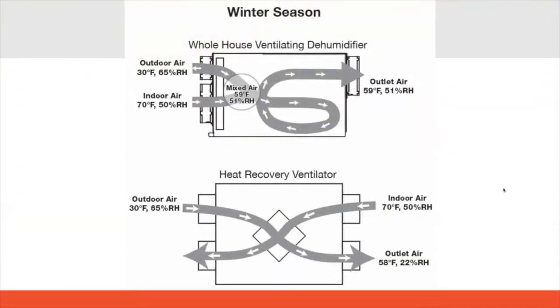So a lot of questions that we get concerning using our dehumidifiers for ventilation is, if it's cold outside or hot outside, I don't want to be delivering that 30-degree air directly into the living space. And the reality is we are mixing with the return air from the living space at the same time. So if we're bringing in, let's say, 50 CFM of outdoor air with our 70-pint dehumidifier, that means we're bringing in 100 CFM from the living space and mixing it in the dehumidifier and then delivering it to the living space.